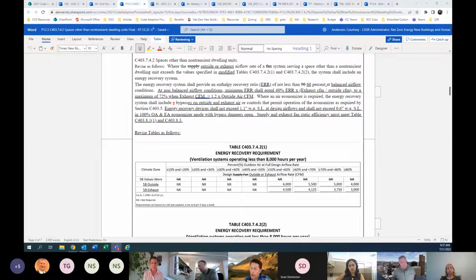Yeah, I agree. And one point that I failed to make earlier is that the section before this section actually requires a 60% enthalpy recovery ratio. But it does not have a sliding scale based on exhaust to outside air CFM. And air pressure drop and those sort of things too. So. Right.